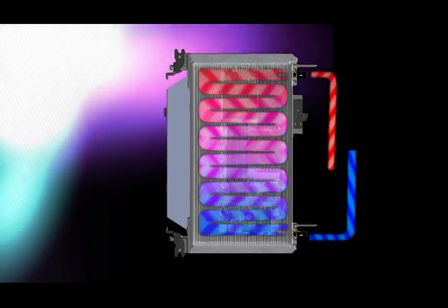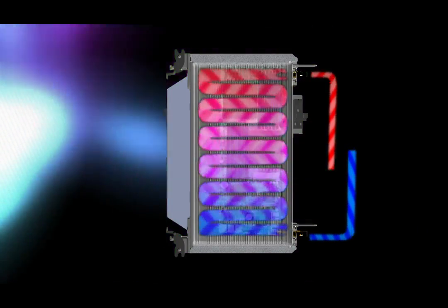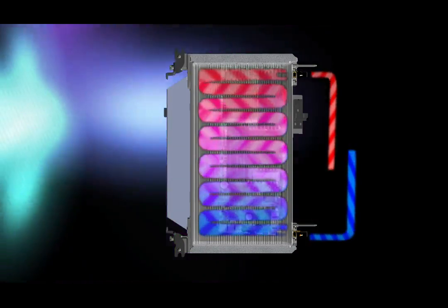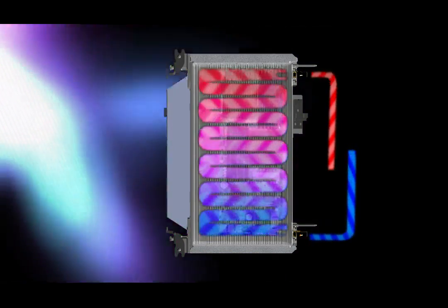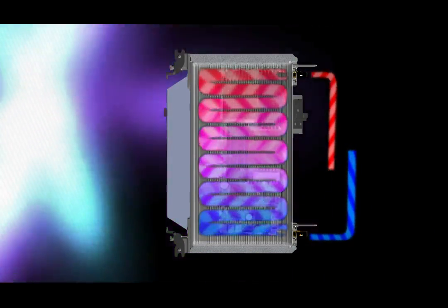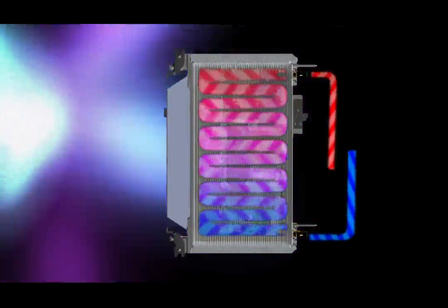Heat is extracted from the Iceotope module by water channels cast into the design. The water used doesn't need to be chilled and can actually be up to 50 degrees C and still be effective. This means that even in equatorial regions, the platform will allow for full-time free cooling anywhere. As a byproduct, the warm output water can be used in other applications, such as building heating.